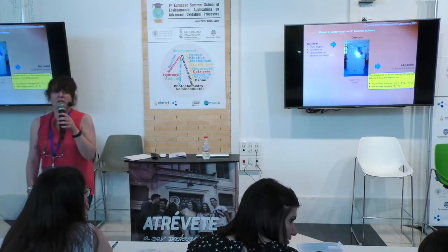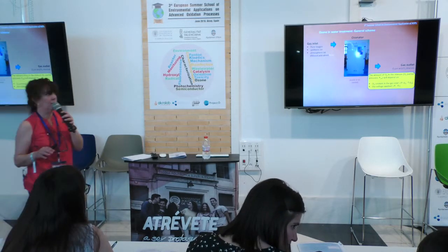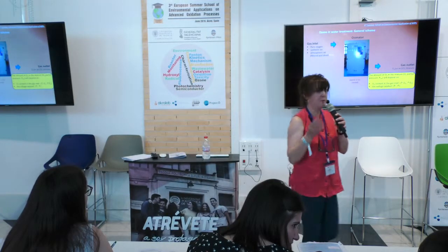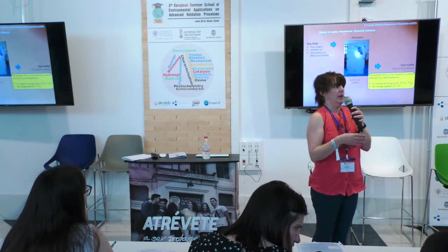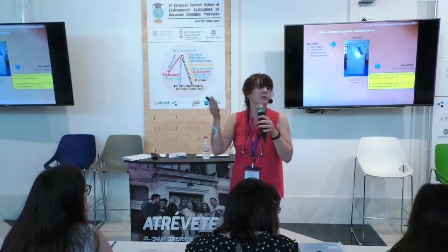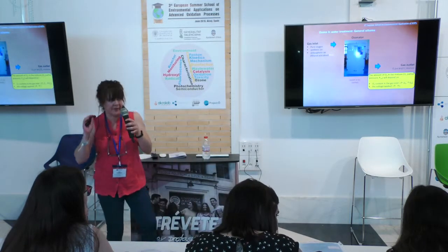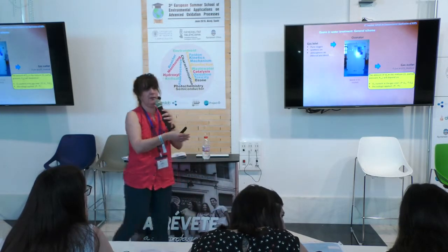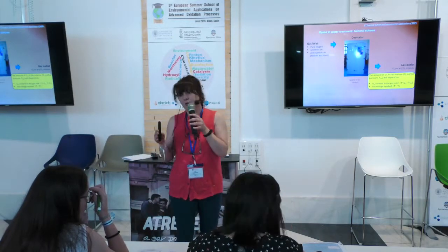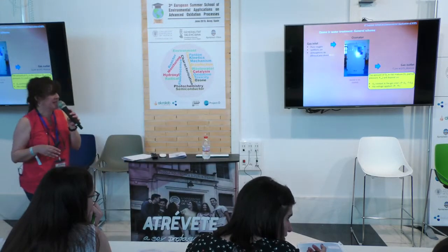Okay, so this will be a general scheme of an ozonation process. We have our gas inlet that can be pure oxygen, synthetic air, or even atmospheric air previously filtered and dried. The gas mixture, air or oxygen, is fed to the ozonator, that is normally water or air cooled to dissipate the heat.